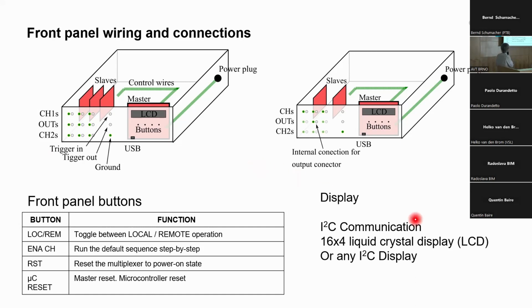Here is the push button operation: local/remote, enable channel to close the channel, and reset the multiplexer. This is a software reset, which just puts the multiplexer into power-on state without erasing the memory of the controller board. There's also a microcontroller reset, which resets everything, so if you've programmed a sequence to run, you have to reprogram it again.